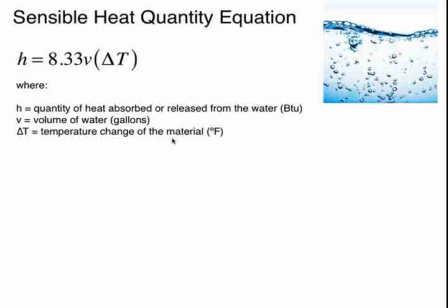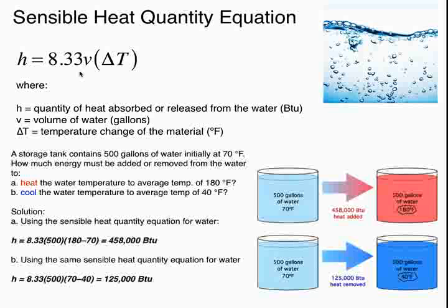Now, the physics of storing heat. The equations are pretty straightforward. The amount of heat that a given volume of water will store is calculated based on the volume, and in this case it will be in gallons for V, and the temperature change of the water. So if we know a temperature change and we know the volume of water, we can just plug some numbers into this formula and come up with the amount of heat that has been put into storage or taken out of storage. And just as an example down here, let's say we start with 500 gallons of water at room temperature, 70 degrees, and we want to know how much heat has been added to take that same 500 gallons up to a uniform 180 degrees Fahrenheit.